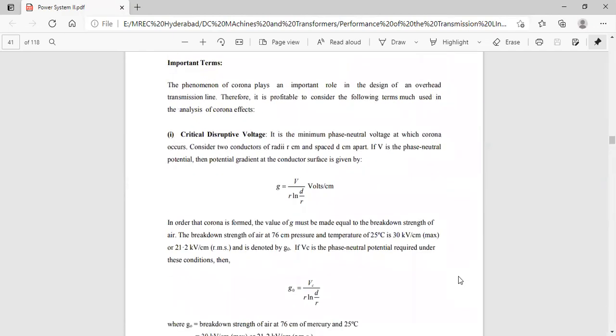Now, what are the important terms used in the corona? The phenomenon of corona plays an important role in the design of an overhead transmission line. Therefore, it is possible to consider the following terms much used in the analysis of corona effect. Due to this corona effect, the performance of the transmission line also reduces, efficiency goes down, and the regulation of the system also goes down. The first one is critical disruptive voltage. It is the minimum phase neutral voltage at which corona occurs.